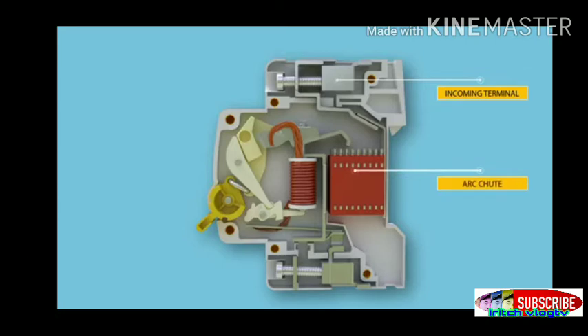Remaining parts of MCB: The incoming terminal is made up of electrolytic copper or silver alloy, and this is where the incoming phase is fixed. Next is the arc chute, a stack of mutually insulated parallel metal plates which divide and cool the arc.